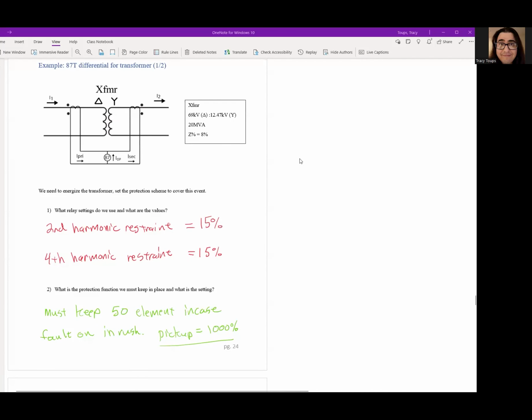All right, welcome back. Let's go ahead and check this differential transformer design example we're working on. So here, first thing we say is we need to energize a transformer. So set the protection because remember, energizing a transformer, you're basically looking at inrush current. So inrush current is always rich in second and fourth order harmonics. So we could just set in the relay a second order harmonic restraint of 15%, a fourth order harmonic restraint of 15%. This will end up blocking the 87 relay from operating during an inrush event.